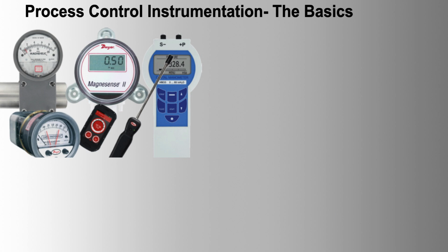4. Installation and placement. Proper sensor placement is critical for accurate temperature measurement, avoiding areas with temperature gradients or hotspots. 5. Calibration and maintenance. Regular calibration and maintenance schedules to ensure long-term accuracy and reliability. 6. Explosion-proof design. Ensure that the instruments are suitable for use in hazardous areas. 7. Heat transfer. Consider the thermal mass and heat transfer characteristics of the sensors and their mounts.